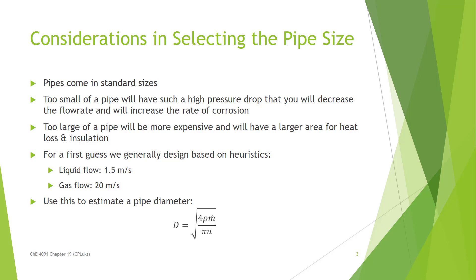What we normally do is use heuristics as a way to get started. I design initially with a liquid flow rate of 1.5 meters per second and a gas flow of 20 meters per second to estimate my pipe diameter. Those standard flow rates are based on good design principles involving the rate of corrosion, but also safety hazards for hearing — there's going to be a lot more noise the higher the velocity is. So these are good solid upper limits to consider, not firm but close.